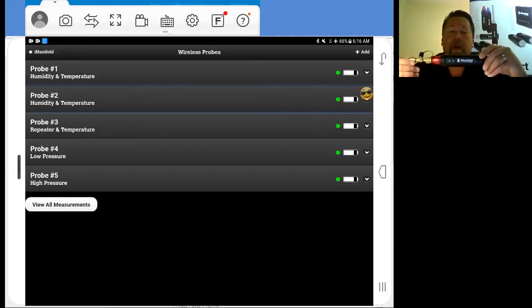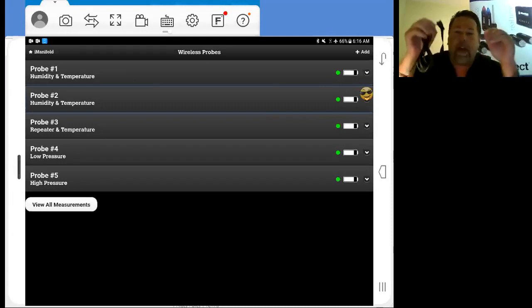On each one of these probes, there are 2 temperature inputs on the side here. The one closest to the tip here is T1. One behind it is T2. Now T1 on this high side probe is pre-mapped to our liquid line temperature. So we're going to go ahead and add our temperatures here.